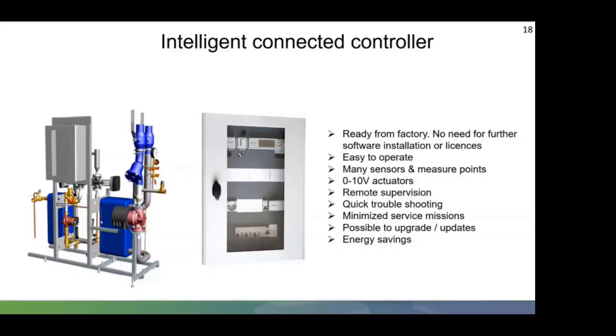This also enables the substation to be viewed, analysed and diagnosed prior to a site visit from an engineer, reducing the time spent on site and the disruption. So if you know roughly what's going wrong, it gives you a better idea rather than having to turn the whole system off. It could be a blockage on the heat exchanger, it could be a pump that's down, it could be a control valve or an actuator that's not working. But it gives the site engineer the tools to pinpoint straight away where the system could be wrong and turn the system on quite quickly and get it up and running within an hour or two, rather than the system being down all day.